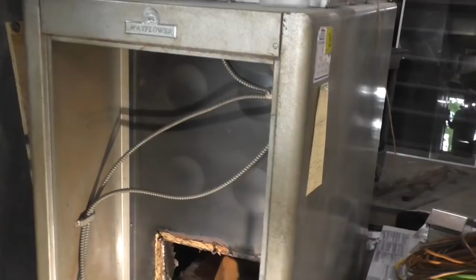And in this case, there is something very wrong. That heat exchanger is almost completely blocked. So all the heat that's supposed to be flowing out the chimney is staying right here and building up. The other thing that does is it shortens the life of the heat exchanger by causing it to constantly remain at the limit of what it's designed to handle. It causes the metal to fatigue, to weaken, and we all know what happens there.